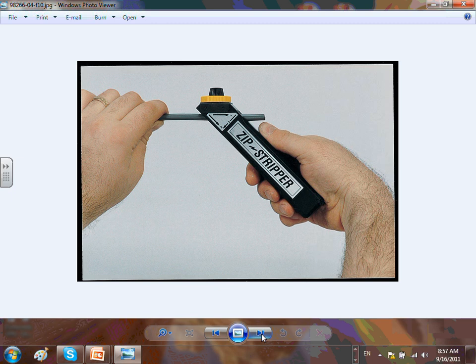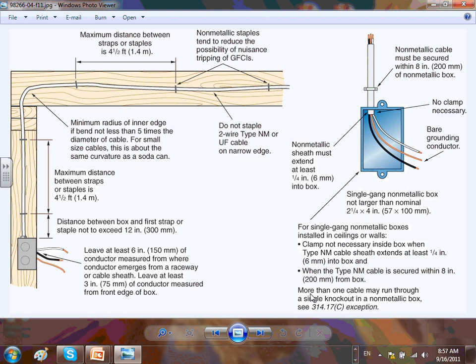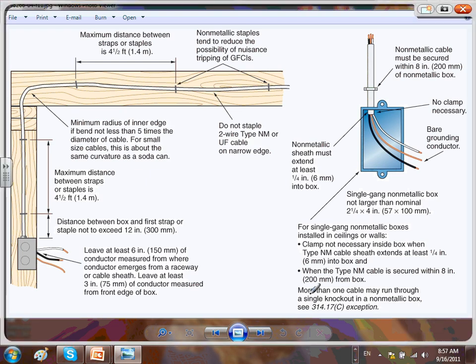Romex, I believe you can get it up to number 6. I don't think you can go higher than number 6 with Romex — it's a very limited application cable. A few things to pay attention to with Romex: you staple them. The distance from the box is 12 inches for a metallic box, 8 inches from a non-metallic box, and in between you have to staple them at every 4.5 feet.